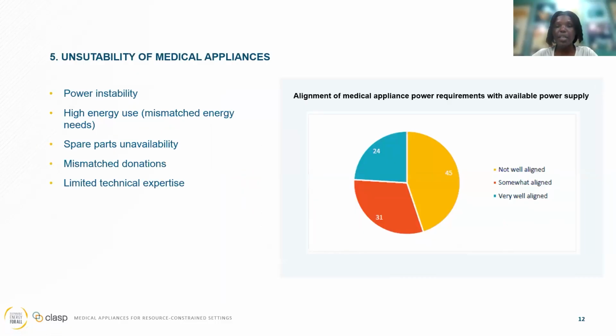Some issues associated with these appliances not being used as they should relate to their suitability in energy-constrained settings. Apart from power instability, we identified high energy use as an issue. For example, autoclaves consume high energy, so this appliance was rarely used in most facilities — they had to wait until they had a certain number of materials before sterilizing, just to minimize energy consumption.